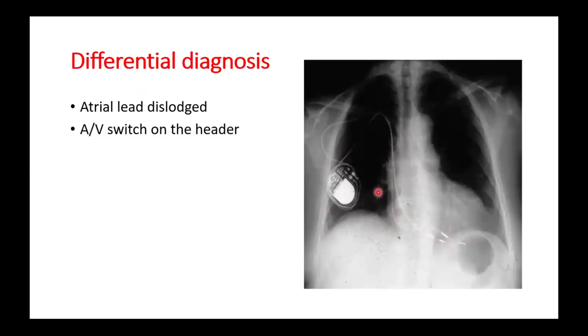And this is the typical ECG of an AV switch. What we can notice here is that it is capturing the ventricle, and after the AV time, then ventricular pacing, because the ventricular lead is placed in the atrial port in the header, and the atrial lead is placed in the ventricular port in the header.